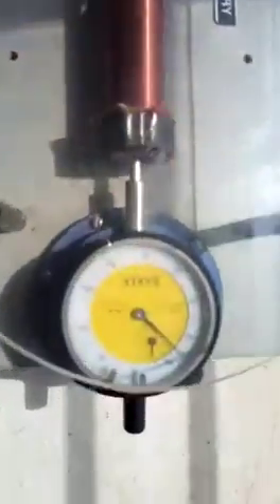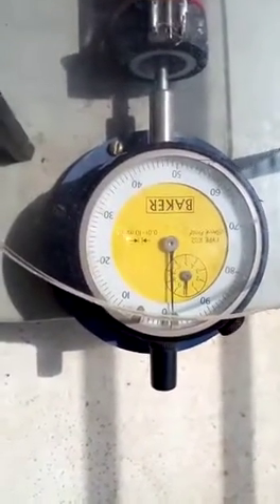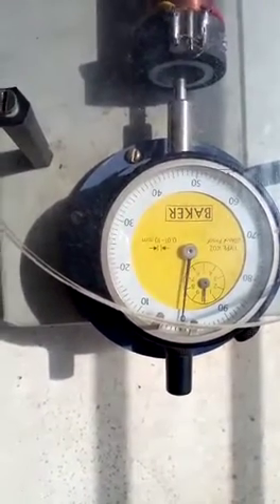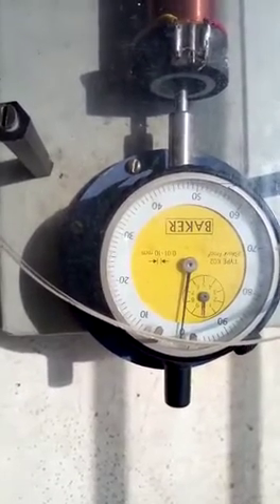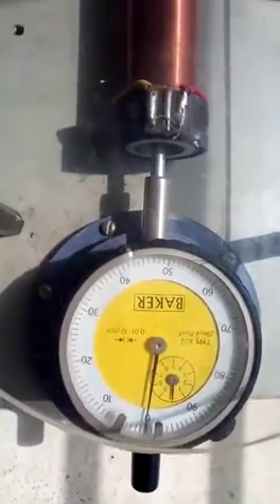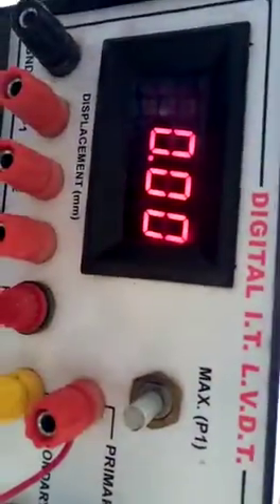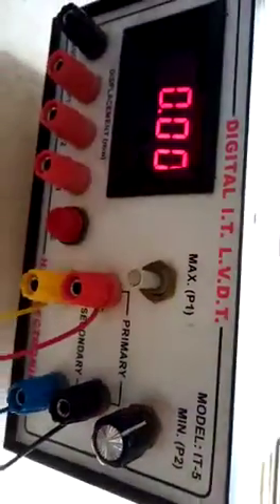Connect the cord of the digital indicator to the main switchboard and switch on the display device. Rotate the knob of LVDT in clockwise direction to displace core until dial gauge comes to 0 position. Now the dial indicator shows 0. If it does not show or indicate 0, use potentiometer marked minimum to get 0 on DPM.